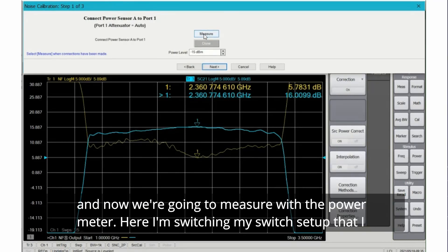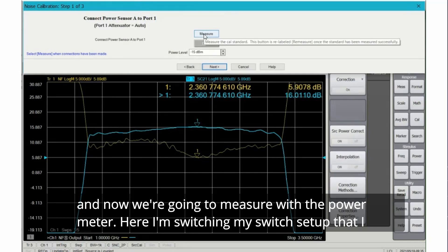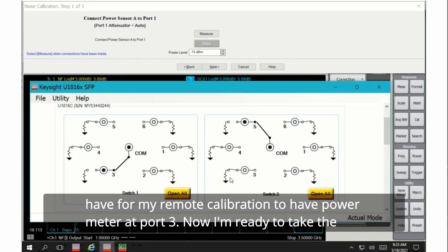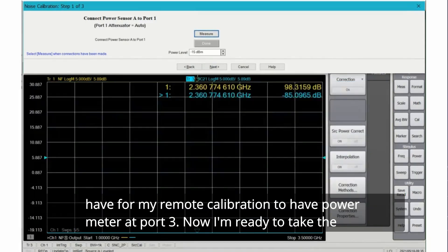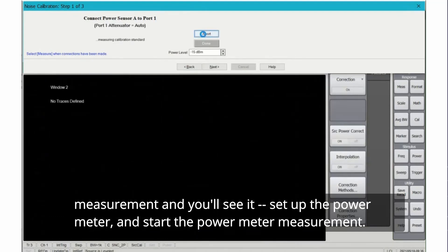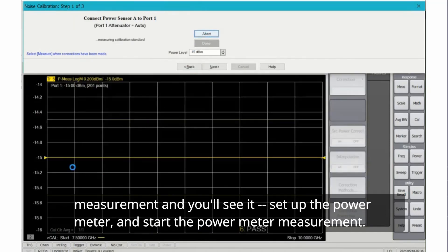And now we're going to measure with the power meter. Here I'm switching my switch setup that I have for my remote calibration to have power meter at port 3. I'm ready to take the measurement and you'll see it set up the power meter and start the power meter measurement.